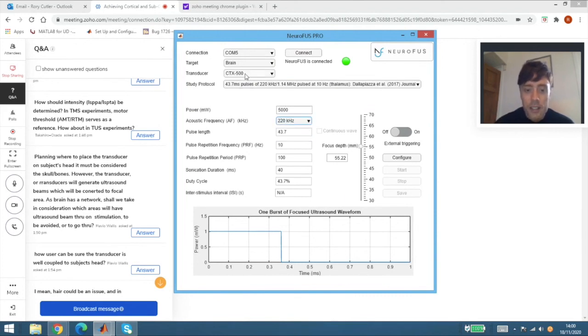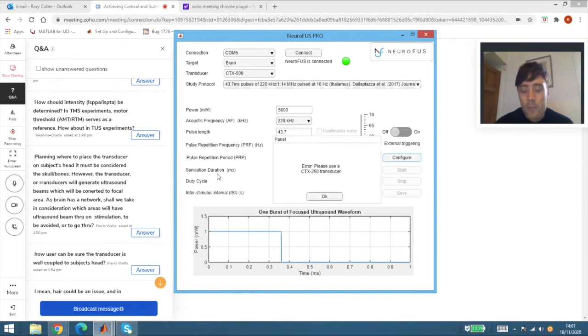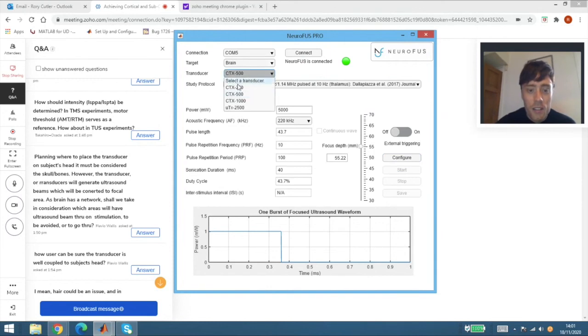So in this case, I need to pick a different transducer. And if you try to do a protocol that you don't have the transducer for, it tells you to use the right transducer. So it gives you the confidence that you aren't, by mistake, thinking you're administering 250 kilohertz on a transducer that's not designed to administer 250 kilohertz.